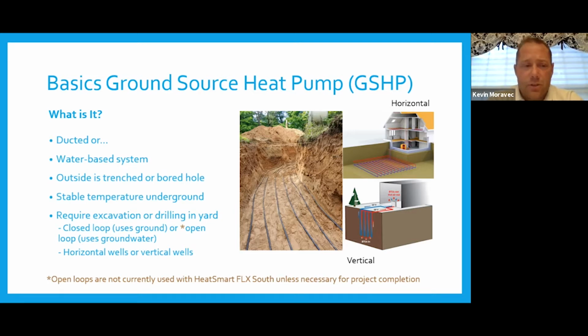The ground temperature is very stable here in Western New York. Vertical systems will see an average deep hole temperature of about 54 degrees. Horizontal systems, at about 6.5 feet depth, range down to 45 or 44 degrees, and in the tail end of summer we can actually see temperatures in the mid 70s.